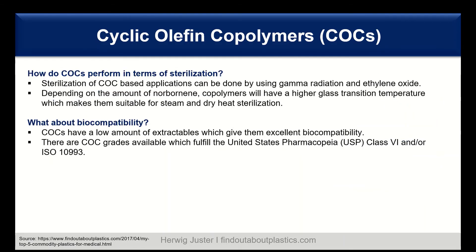How do COCs perform in terms of sterilization? There are several options: sterilization can be done using gamma radiation and ethylene oxide. Depending on the norbornene content, copolymers with higher norbornene will have a higher glass transition temperature, making them more suitable for steam and dry heat sterilization. Regarding biocompatibility, COCs have a lower amount of extractables, which gives them excellent biocompatibility.